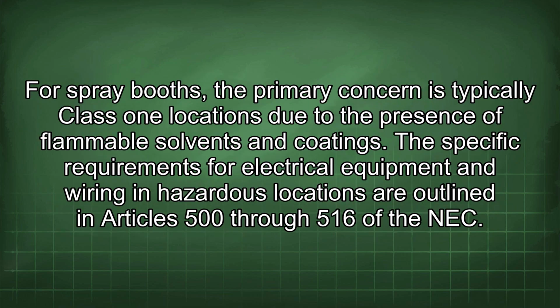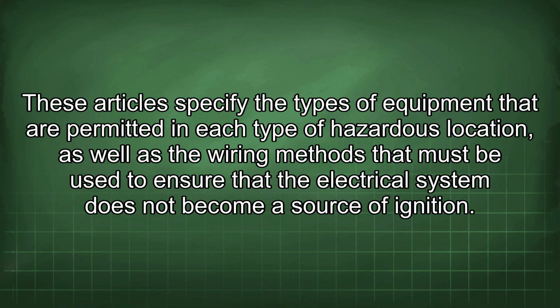For spray booths, the primary concern is typically Class 1 locations due to the presence of flammable solvents and coatings. The specific requirements for electrical equipment and wiring in hazardous locations are outlined in Articles 500 through 516 of the NEC. These articles specify the types of equipment that are permitted in each type of hazardous location, as well as the wiring methods that must be used to ensure that the electrical system does not become a source of ignition.